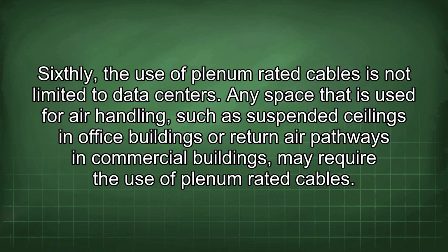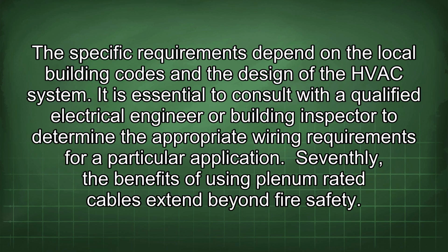Sixthly, the use of plenum-rated cables is not limited to data centers. Any space that is used for air handling, such as suspended ceilings in office buildings or return air pathways in commercial buildings, may require the use of plenum-rated cables. The specific requirements depend on the local building codes and the design of the HVAC system. It is essential to consult with a qualified electrical engineer or building inspector to determine the appropriate wiring requirements for a particular application.